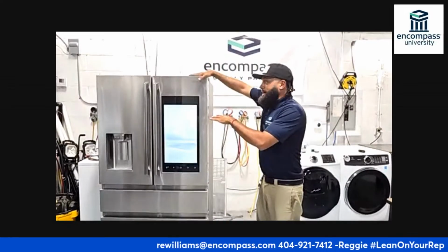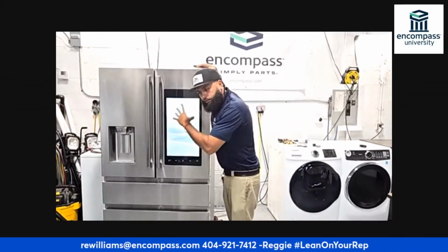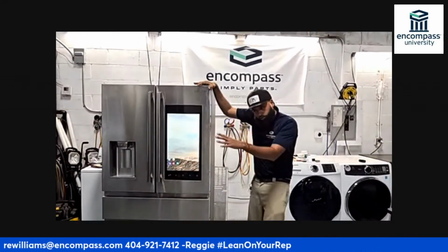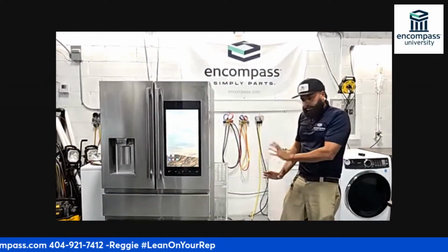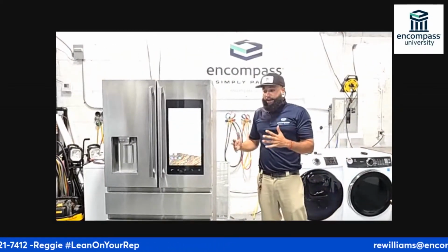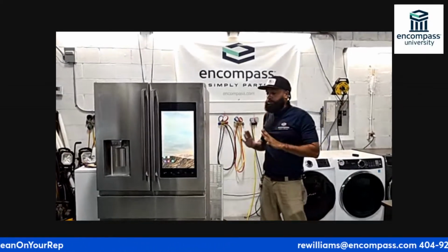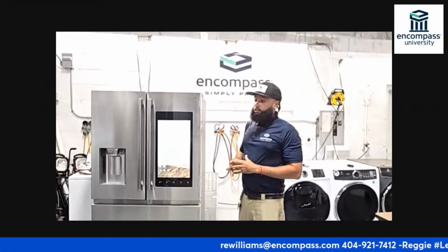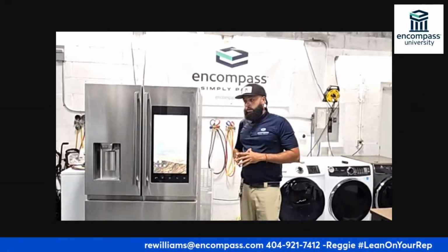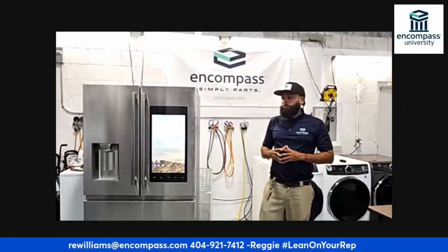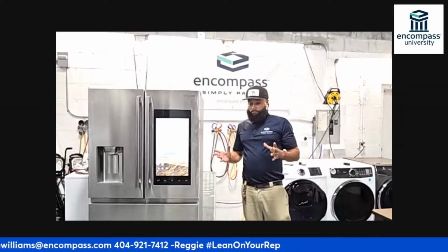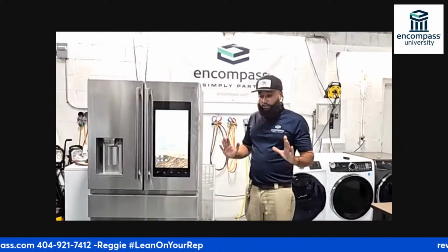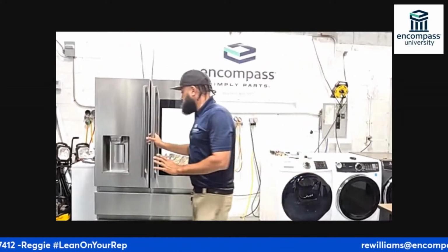So again, remember guys, you want to get in here, listen for the fans, check frost patterns, make sure everything is good. But now that you did all that, we checked every possible thing, we've got to get into the sealed system now. But I always tell guys, before you get into the sealed system, take the covers off.